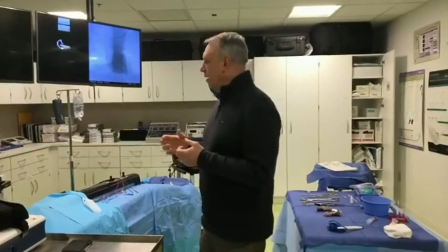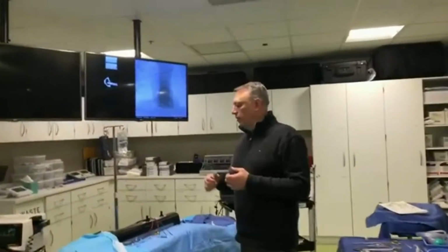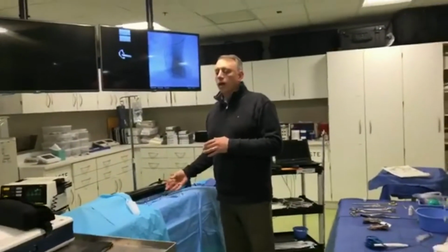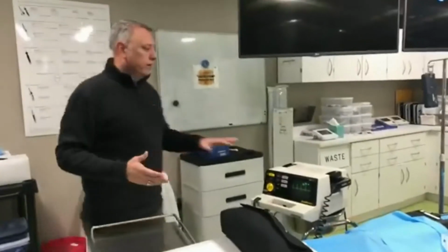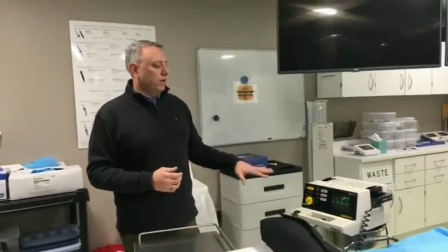Also, they'll have to test the wires that were put inside the patient's heart. We'll have the ability to simulate connecting cables to simulated wires here. They'll have to test certain measurements and see how the patient's heart rhythm reacts to that. In the simulator we have the ability to run a variety of different patient rhythms through the computer to the simulator, and it gets displayed here.